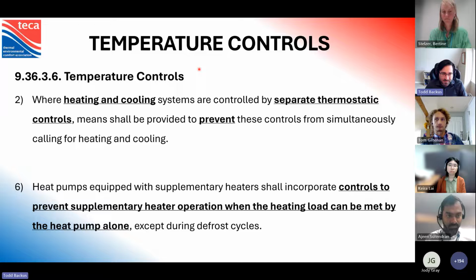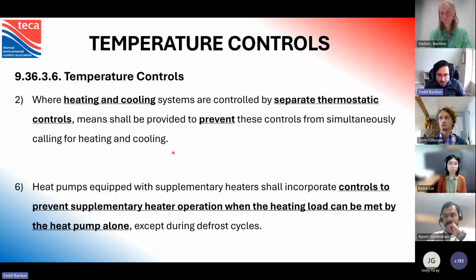Now, one thing that catches people off guard is there are a bunch of HVAC requirements in section 9.36. So 9.36.3.6 temperature controls: where heating and cooling systems are controlled by separate thermostatic controls, means shall be provided to prevent these controls from simultaneously calling for heating and cooling. So we might see this in a situation where you have a hydronic system. So let's say you have radiant floor heating and you've installed a ductless mini split system. Well, there are certain situations where your hydronic heating might be calling for heat at the same time that your ductless mini split system is calling for cooling. So you are actually supposed to have some means of preventing that from happening. And I have seen it happen in real life.